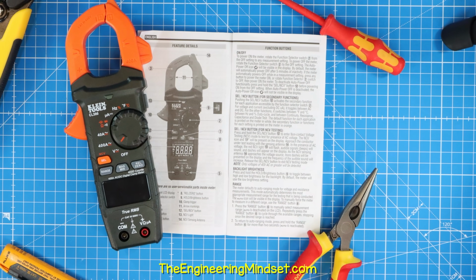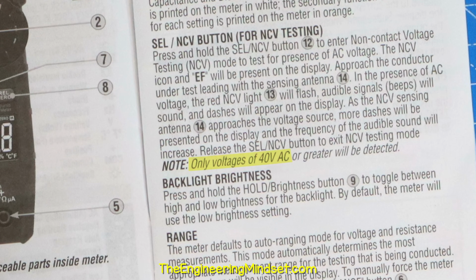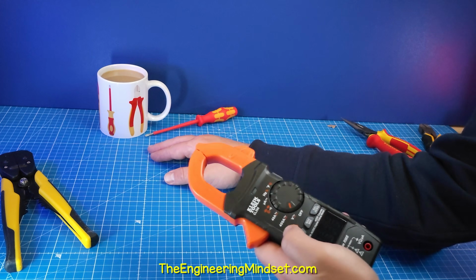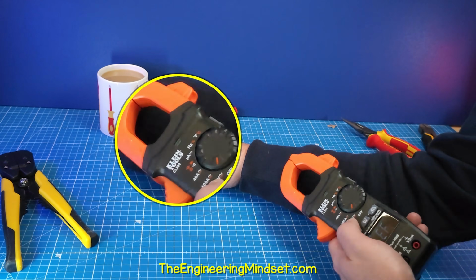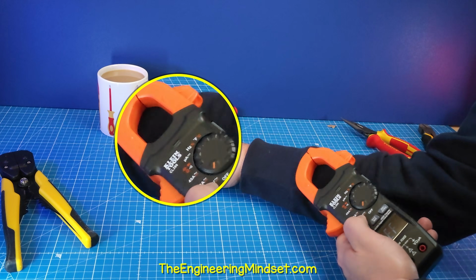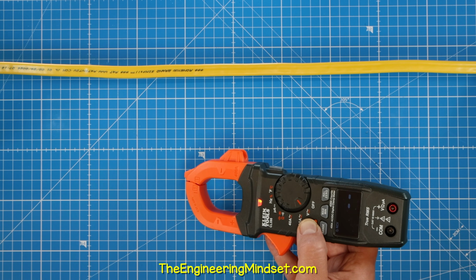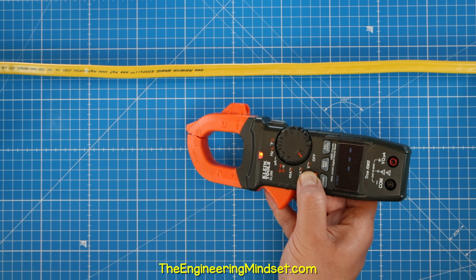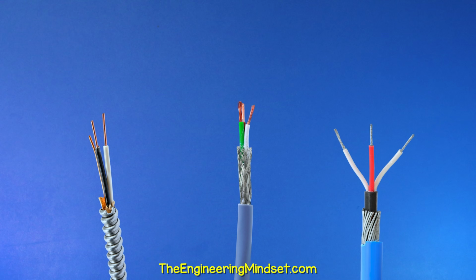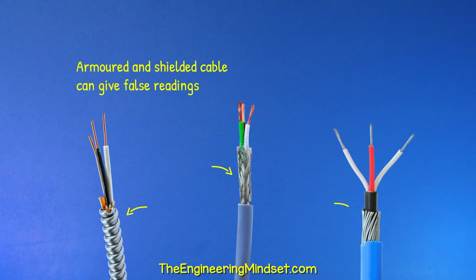You should also check what the voltage range is for your device. Notice that when I move this meter, it indicates that my sleeve is energized. So be careful of false readings. It will pick up other energized wires and equipment if they are too close, and it might not detect voltages in shielded wires. So proceed with caution.